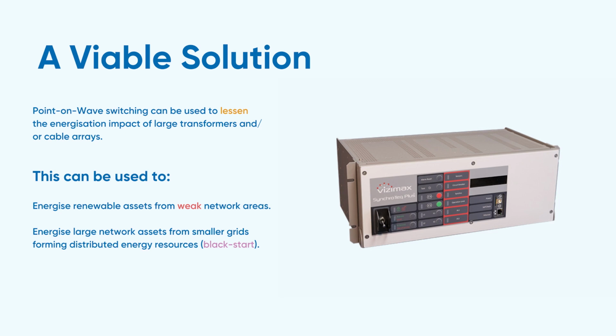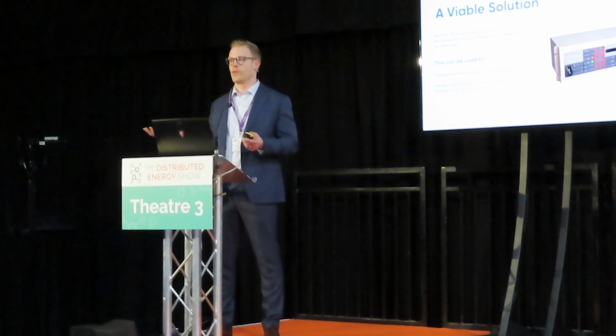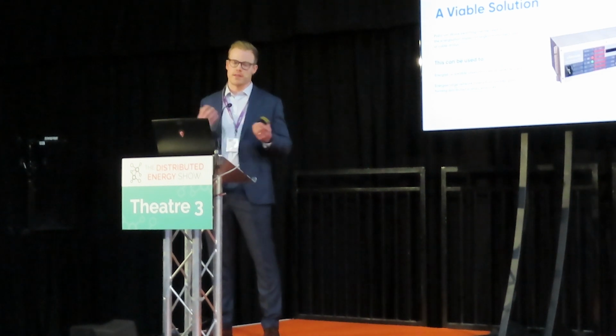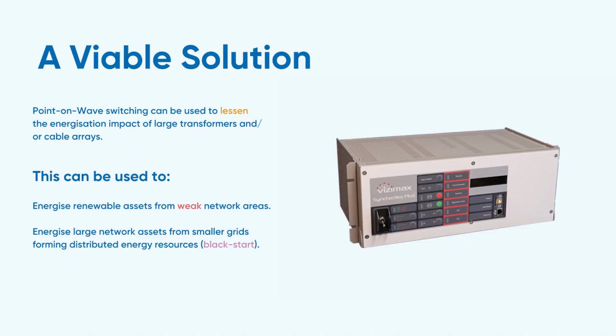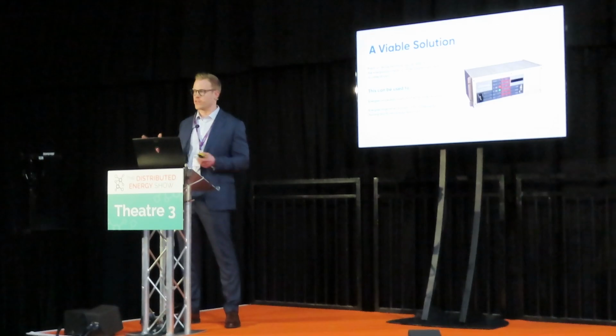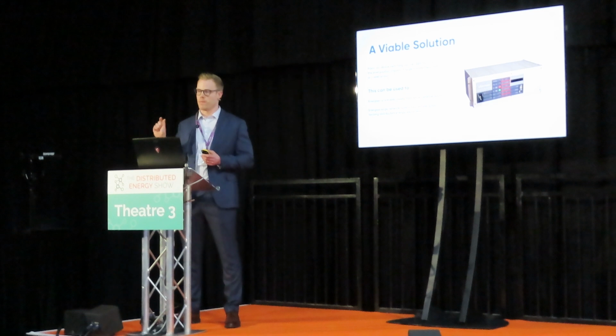To kind of give you an overview of point-on-wave switching, this is a typical relay, as it would look. It's an electronic device, and it effectively becomes a middleman between your close and open controls for your circuit breakers. These circuit breakers could be controlling transformers, cables, and it becomes a middleman between those controls and the circuit breaker to control the precise moment that that circuit breaker closes and we have electrical conduction to within 1 millisecond.